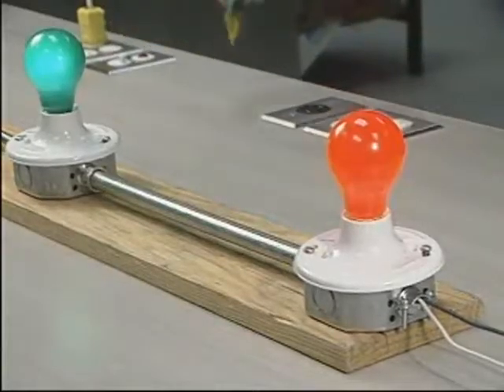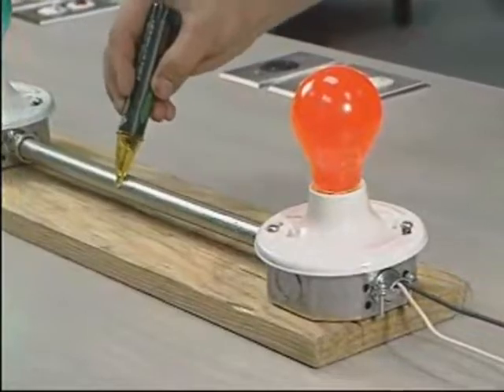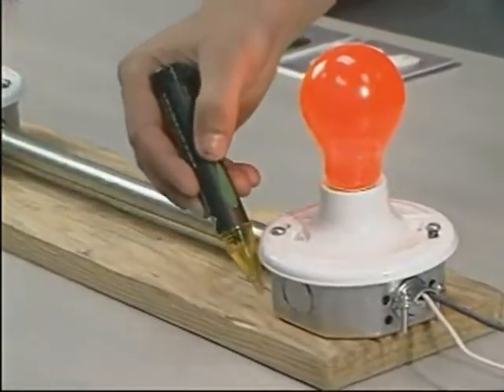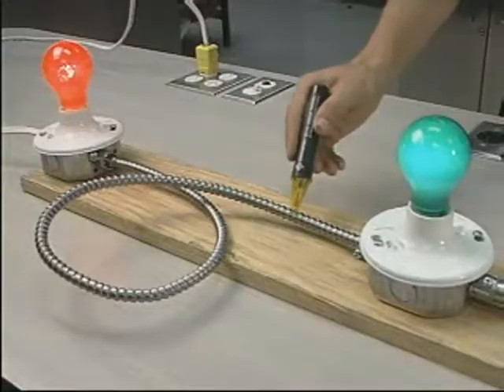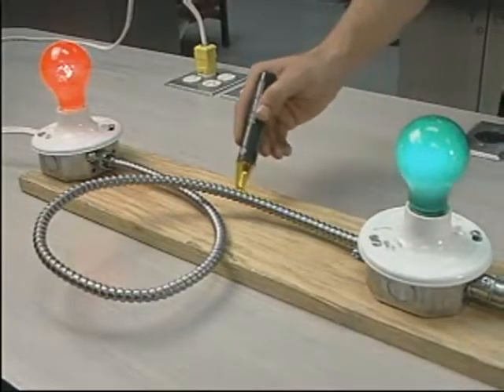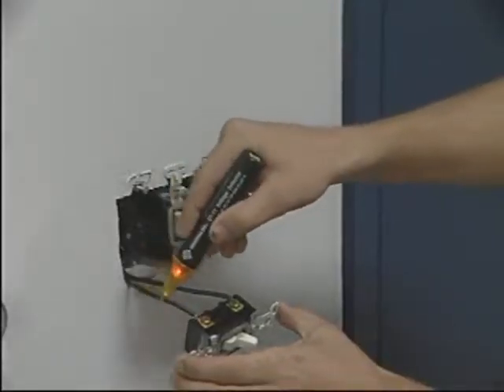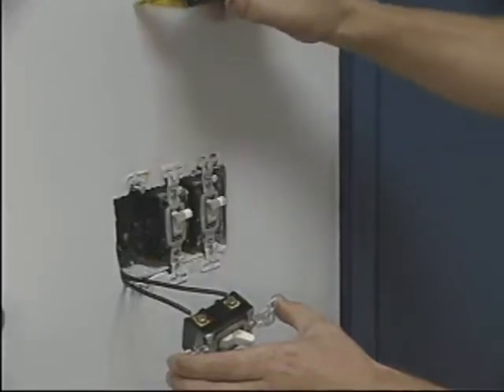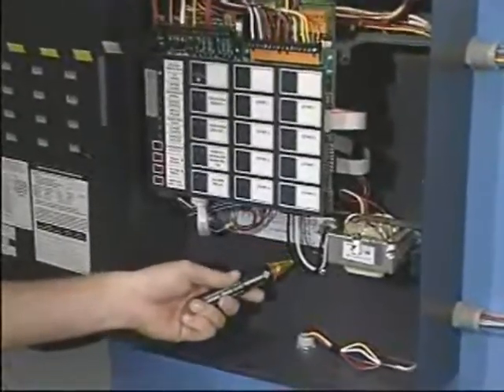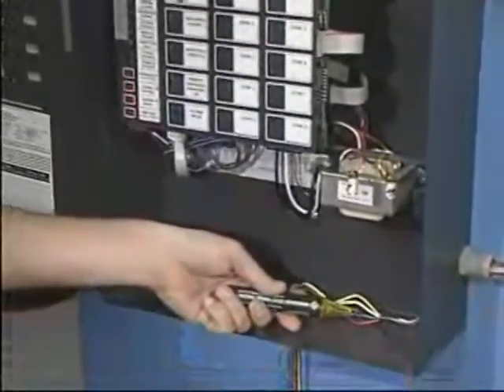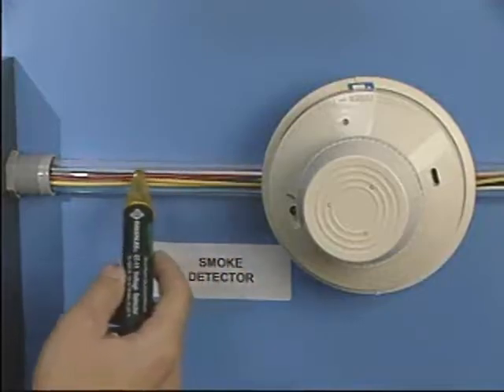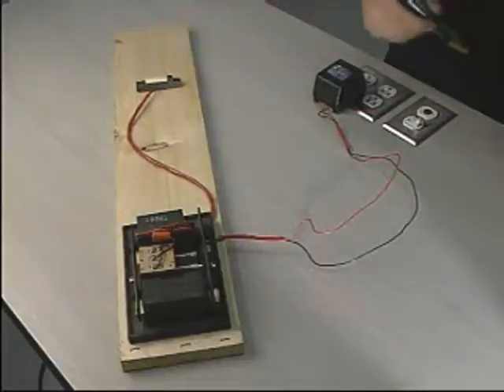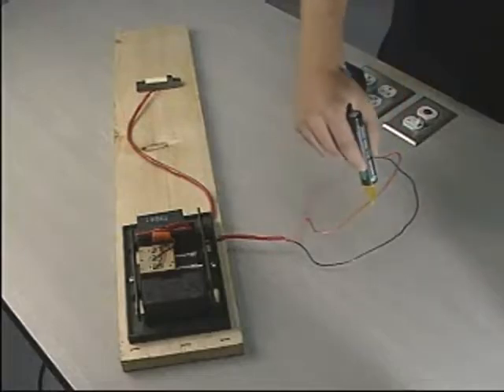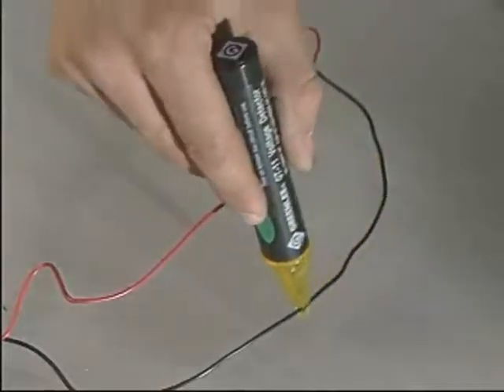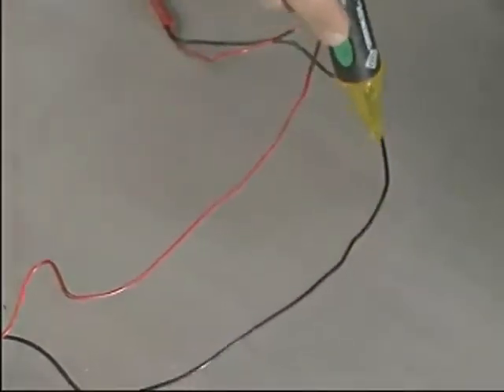It is important to note that all non-contact voltage detectors have limitations. It will not detect the presence of voltage through metal tubing or metal enclosures, in armored or shielded cables, or behind drywall. It will not detect DC voltage as in fire alarm circuits. It will not detect low voltage AC below the rated 50 volts AC, as in this 16 volt AC doorbell circuit. When working in temperatures below 0 degrees Celsius, keep the unit warm.